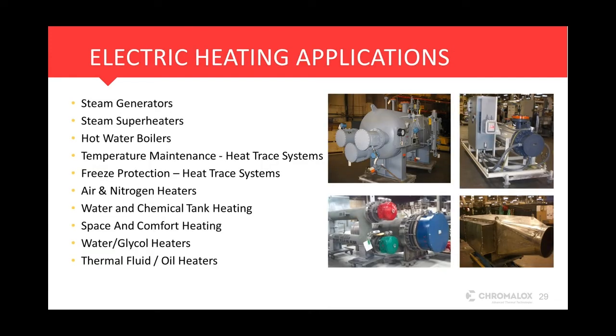I mentioned at the beginning I'd be focused on steam, just to talk about the technology and how it compares, because we're talking about decarbonization and replacing fuel-fired systems, and steam generation is prevalent across a number of industries, so I thought that was a good one to focus on. But the core concepts of what electric offers don't stop at steam generation. It applies to any thermal process, whether it's steam generation, superheating that steam, hot water boilers, air and nitrogen heating, water, or chemical processes. The core technology of electric uses metal sheath protection, and you can choose from any number of chemical-resistant metal grades, so it doesn't matter how nasty the process is - these electric systems can be catered to still get the same benefits we just discussed. You also have temperature management and freeze protection with heat trace systems, which still operate on the electric premise.